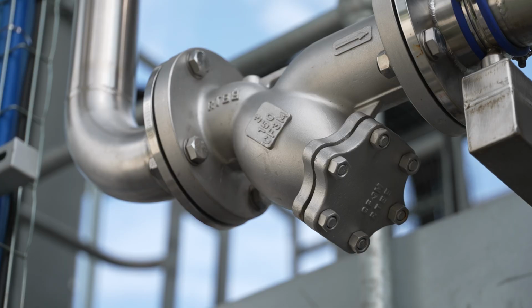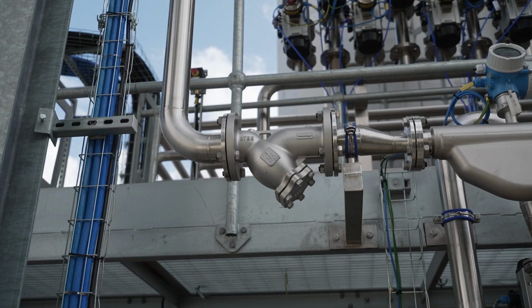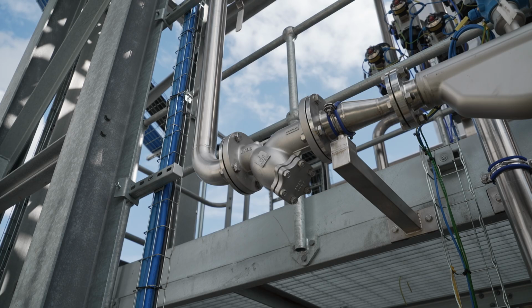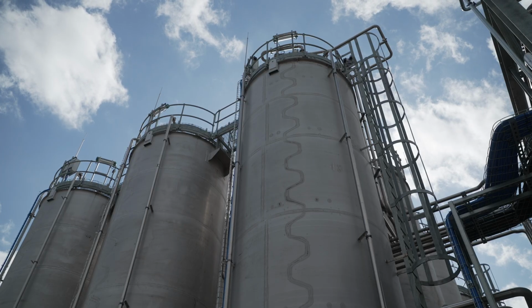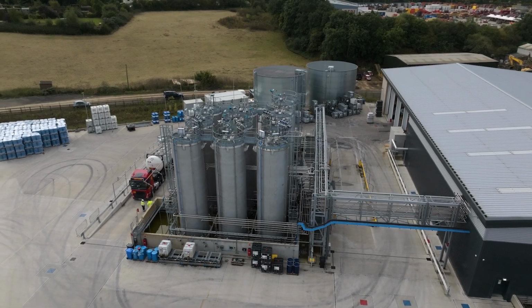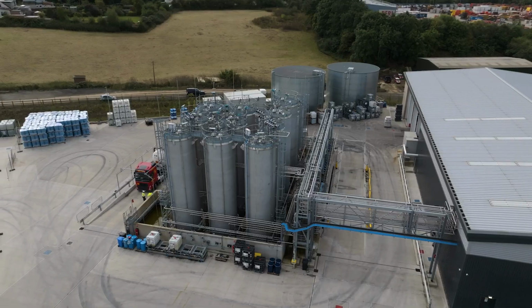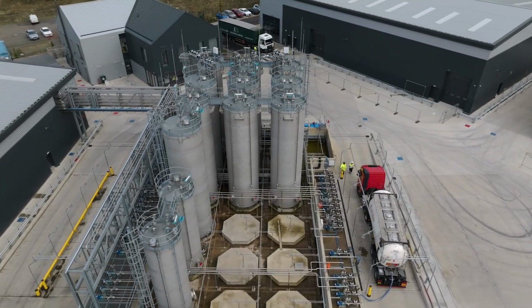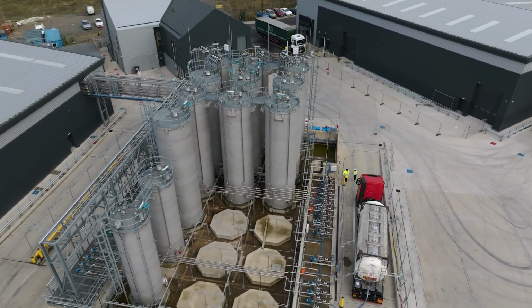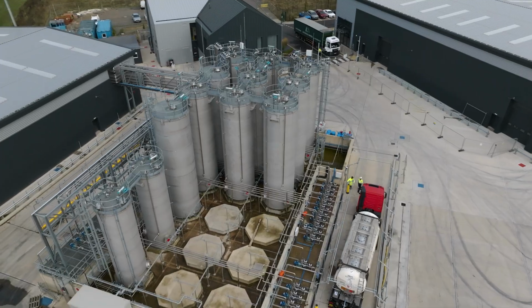Installing filters far enough upstream of discharge points can avoid problems by providing a sufficient liquid residence time greater than the specified charge relaxation time of the liquid. For dispersing operations, the conductivity of the liquid should be raised before particulates are added. If possible, conductive liquids should be added first.